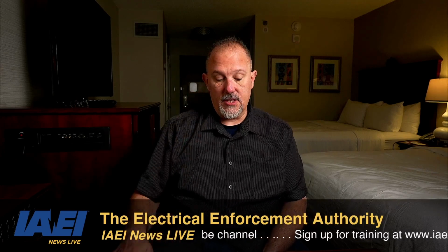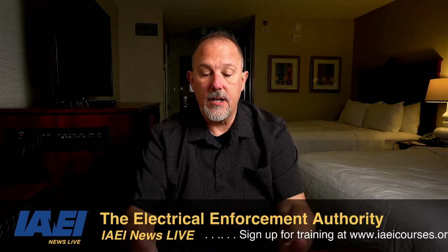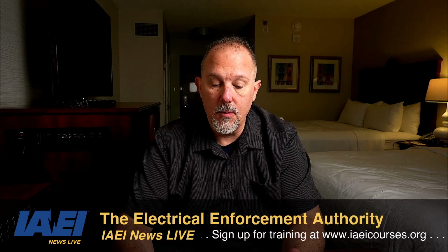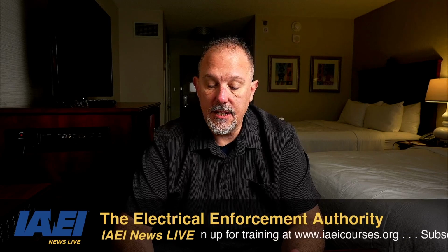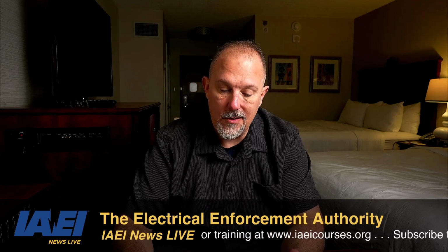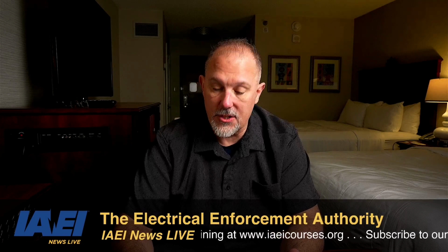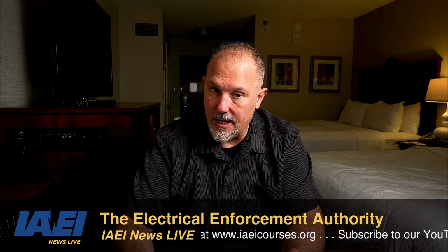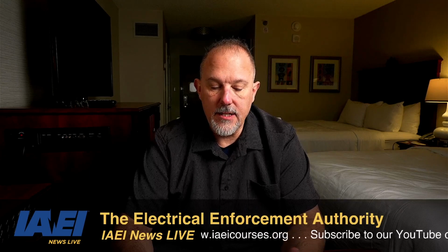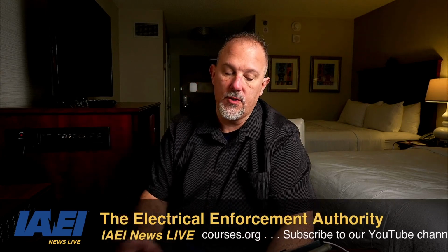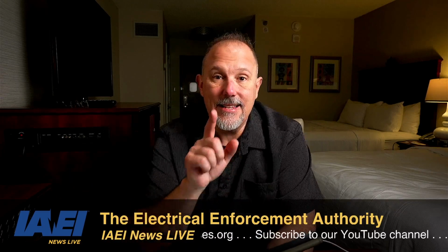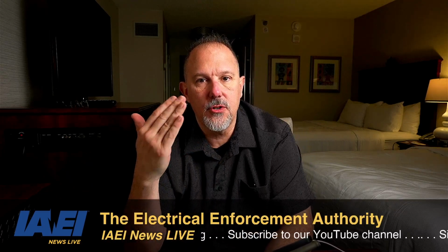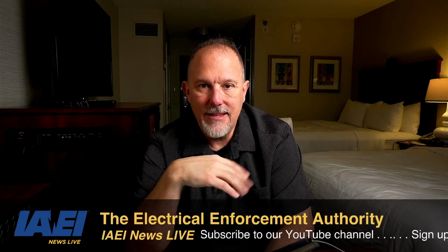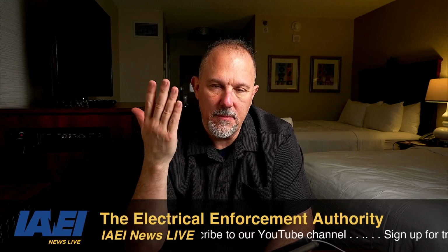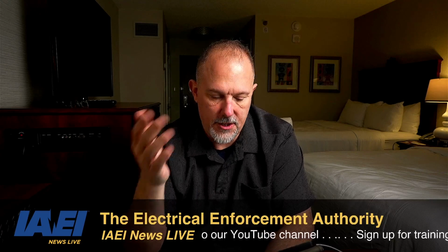Oh, disconnecting means. Let's talk about the disconnect. 445.18. Generators other than cord and plug portable generators shall have one or more disconnecting means. Each disconnecting means has to simultaneously open all associated ungrounded conductors. Each disconnecting means shall be lockable open in accordance with 110.25. That doesn't mean that if you have a disconnect that can also be locked in the closed position, that doesn't apply. You just have to be able to lock it in the open position.